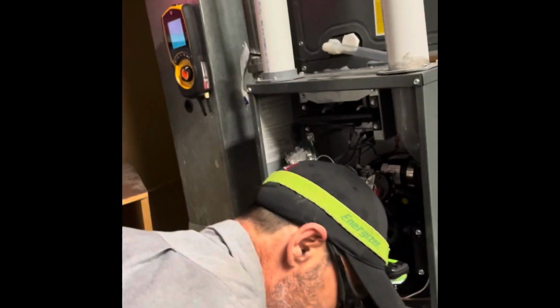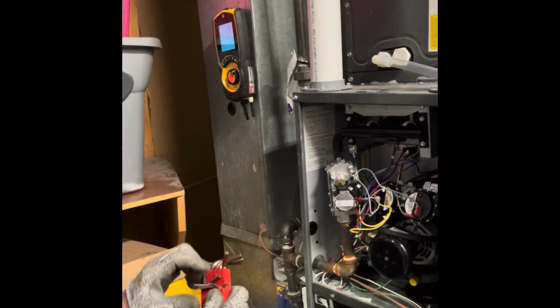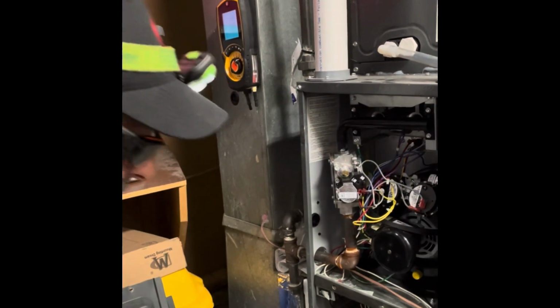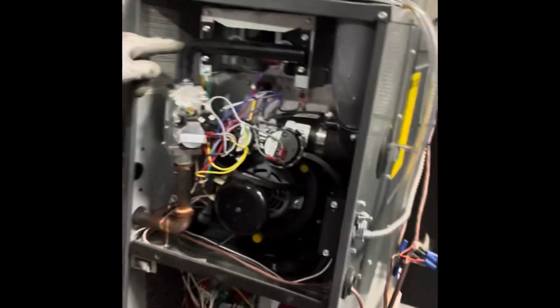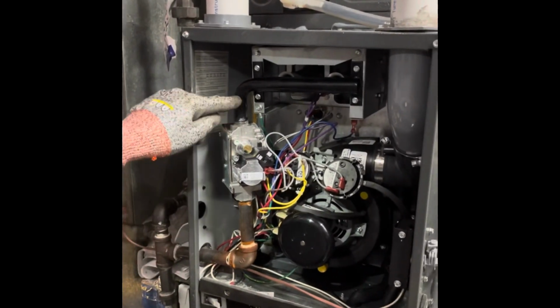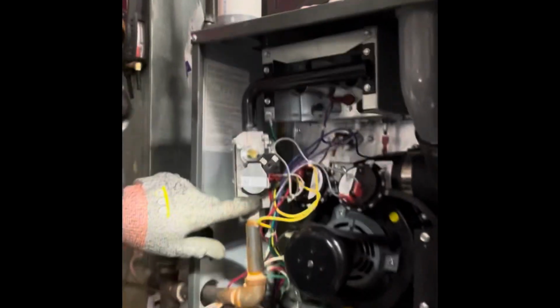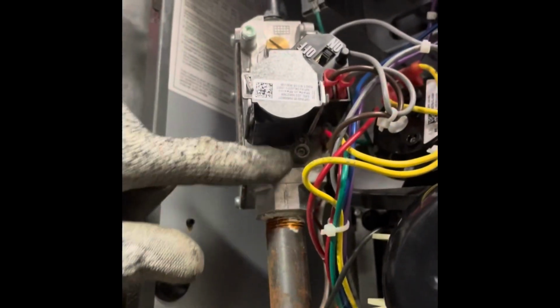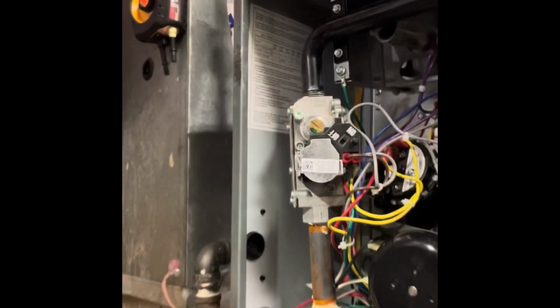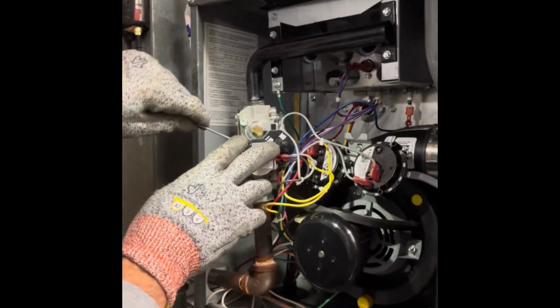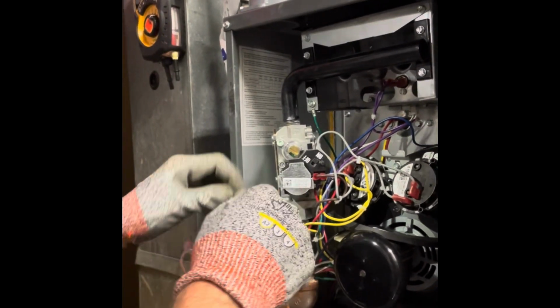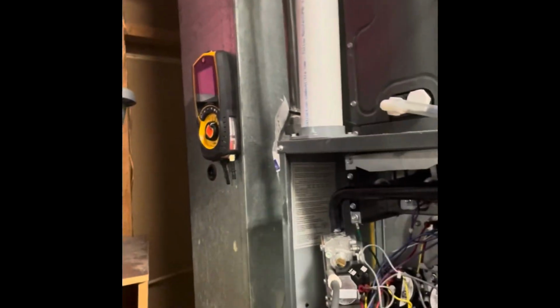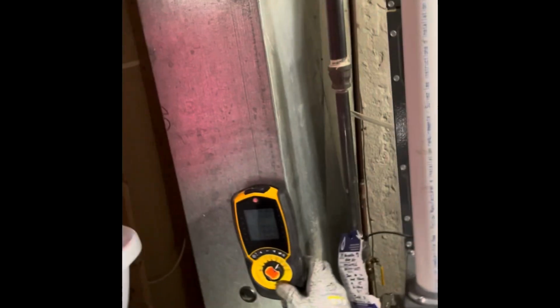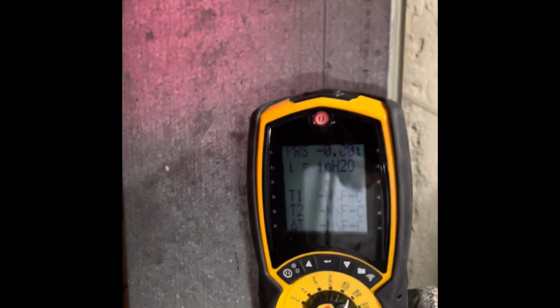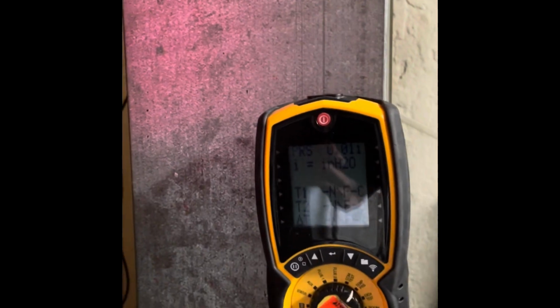And I'm just going to get a little Allen key. I've got to tap into the gas valve so that I can check our pressure. Every gas valve has 2 ports on it. The port closest to our manifold here is going to allow us to check manifold pressure. If we look down here, we've got another port. That one allows us to check street pressure. So on a maintenance, I'm concerned about manifold pressure. I want to know what that's doing before I check anything else. So I'm going to hook this little hose up to my device here. This is going to let me check his gas pressure. So we'll put that like so.